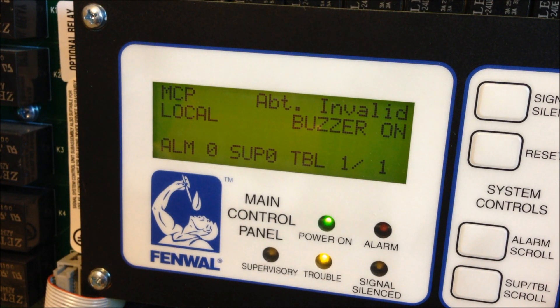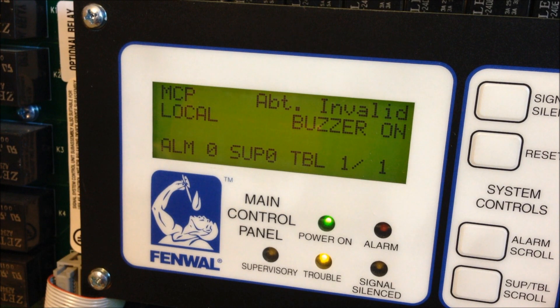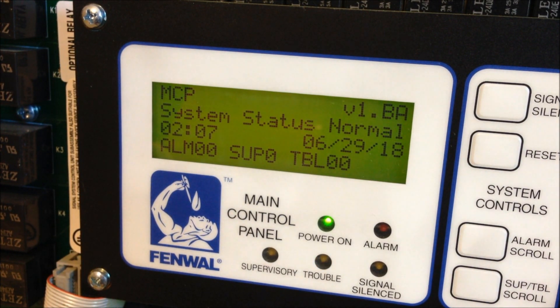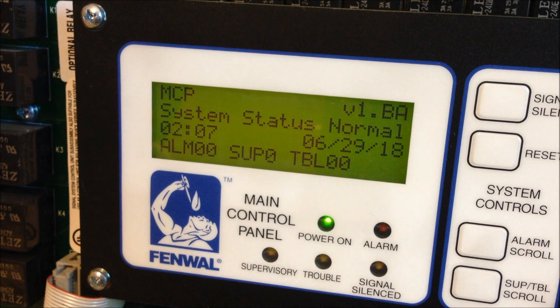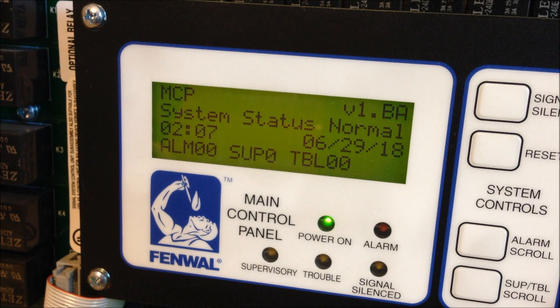If I go ahead and press the abort button, we get an abort invalid trouble and the panel buzzer sounds. If I let go, that trouble just restores — it's not a latching trouble. As you can see, if somebody just happens to tap this button briefly, nothing significant is going to happen.